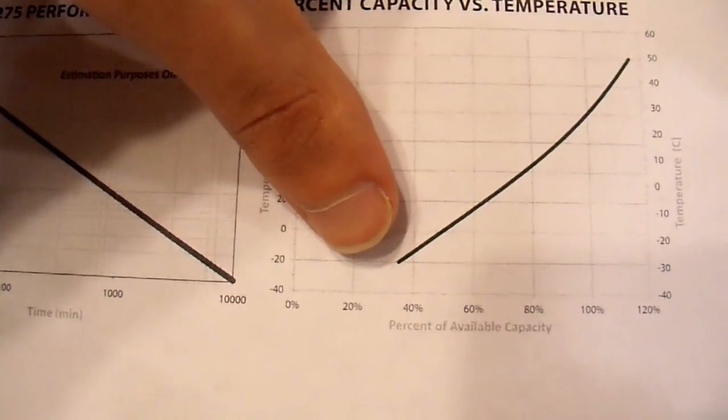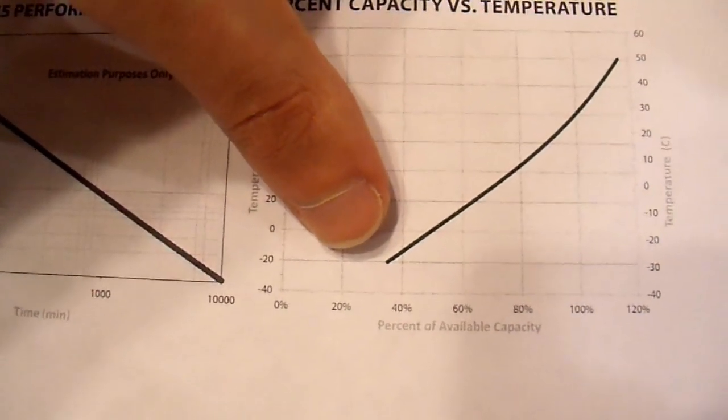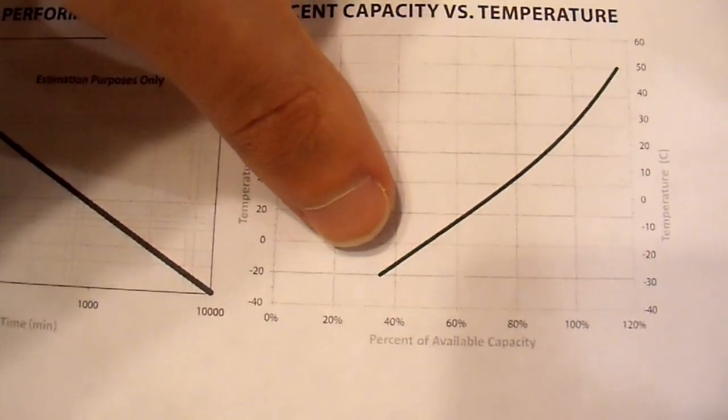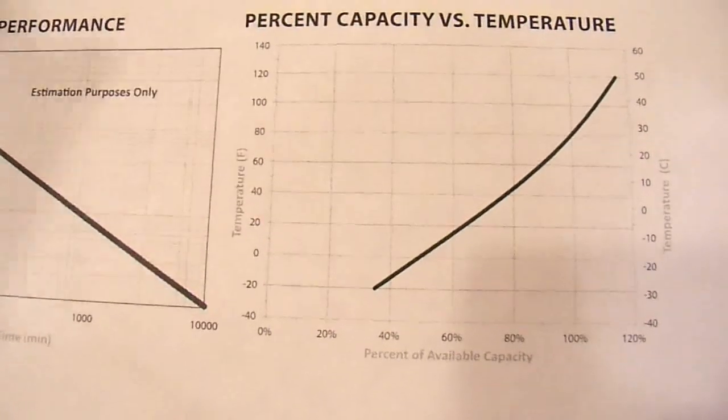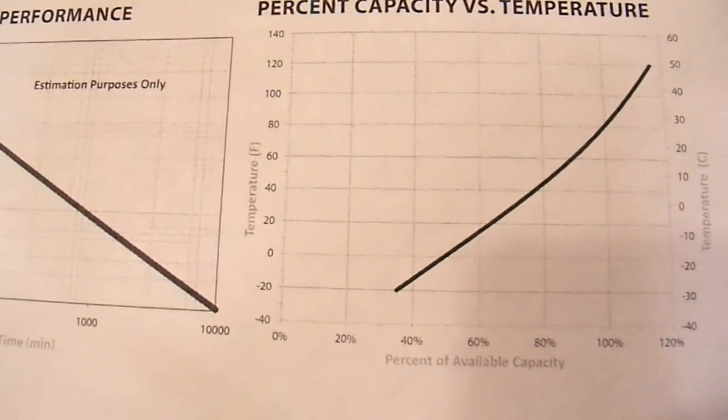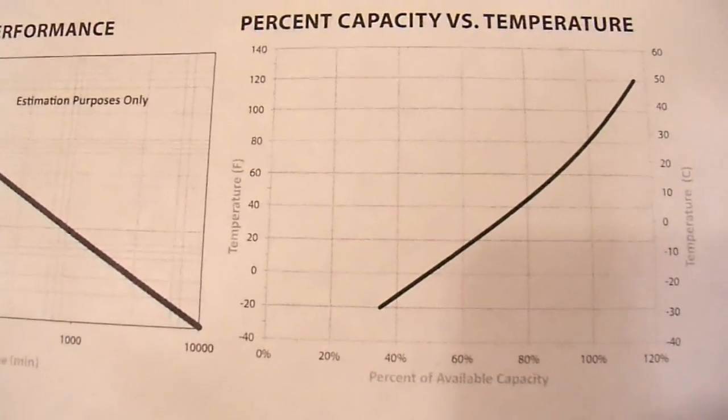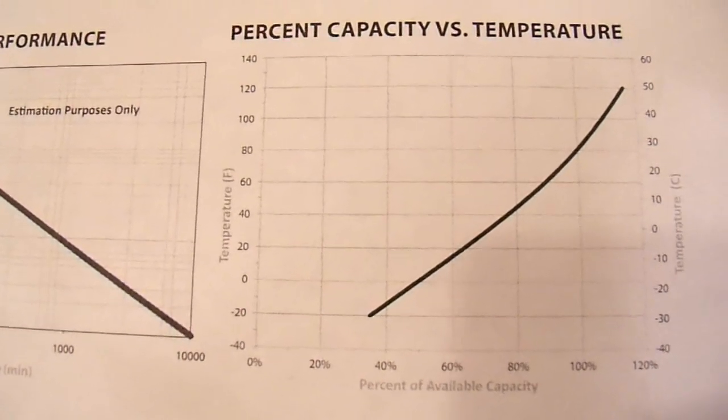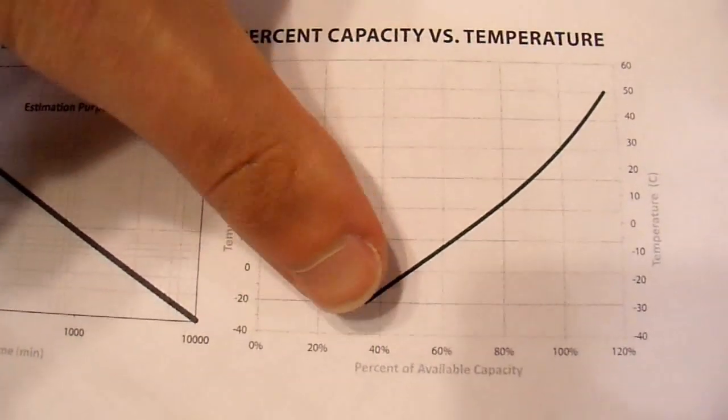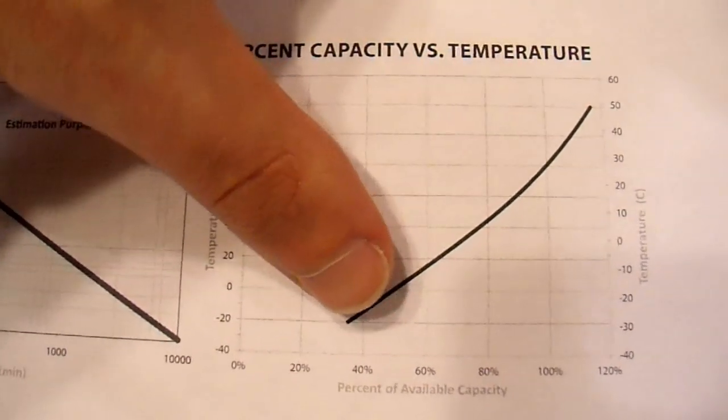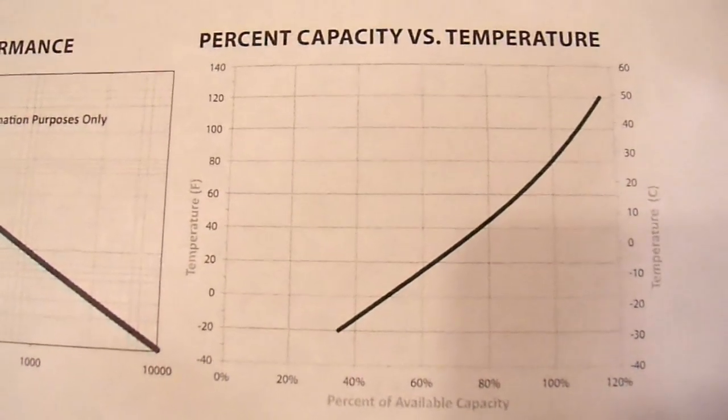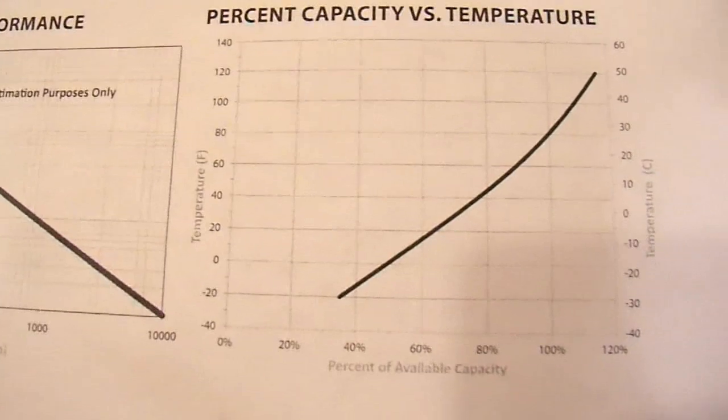But down here, when it's minus 20, your internal resistance of that battery, and chemical resistances, are very, very high. And you may only be able to discharge it down to, say, 70% state of charge. And after that, there's not enough ions left in that electrolyte solution, your resistance is too high, and you can no longer effectively use the rest. If you take this battery that is no longer useful at your current draw and bring it indoors, you can then continue to use the rest of it.